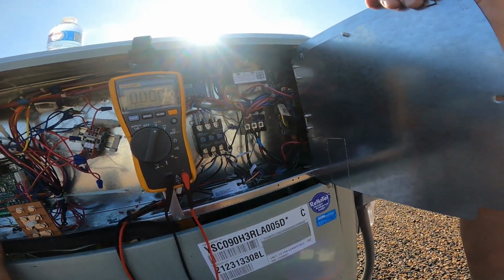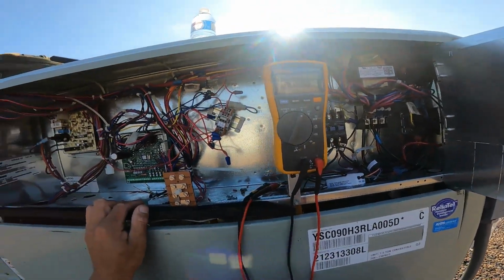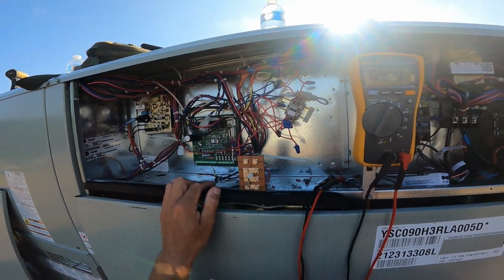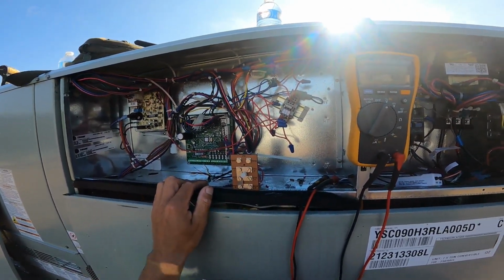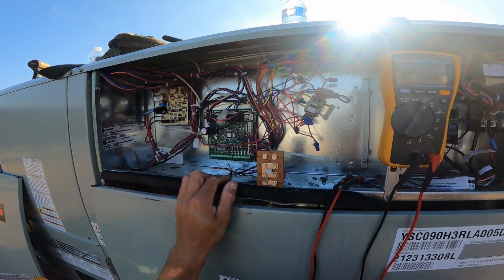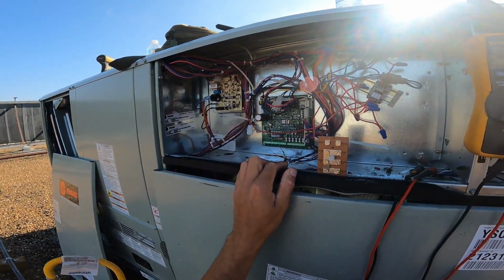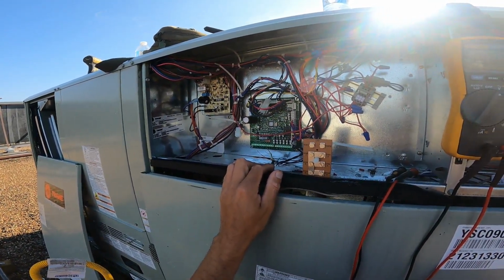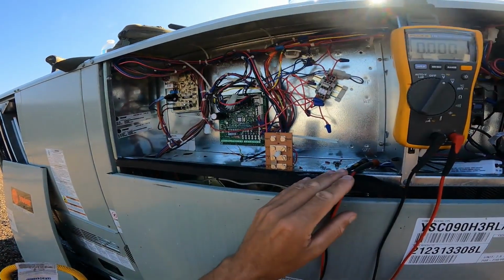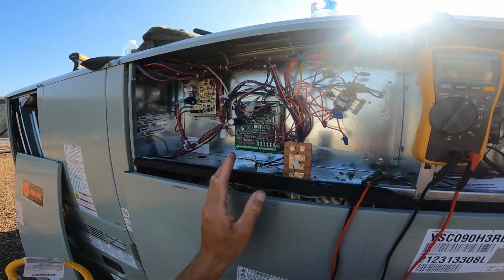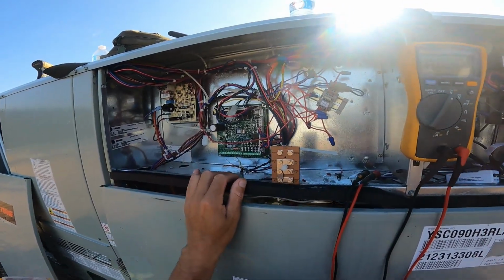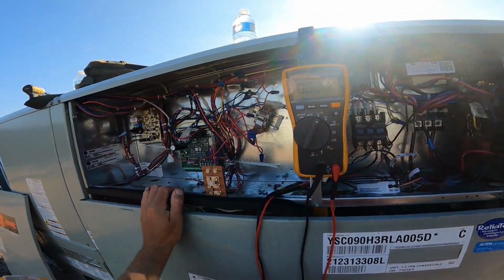Very few situations have I actually had to use them, and that would be like restaurants on the cook lines where they are actually trying to cool in the middle of winter because it gets really hot, big time heat load. In that situation, not only do we need the crankcase heater, but we also need a fan cycle switch, which we install so we can create head pressure. Enough of that mumbo jumbo.